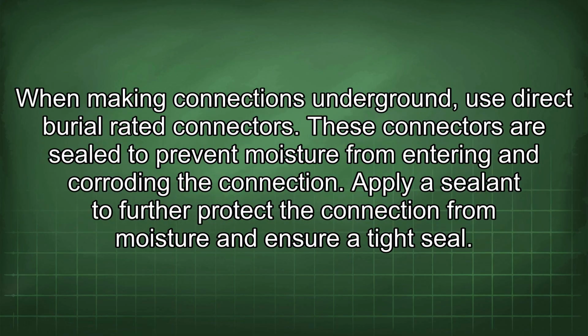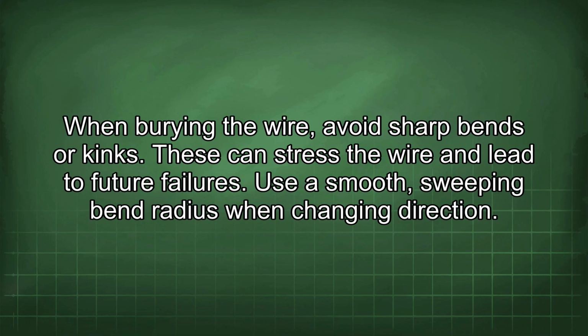When making connections underground, use direct burial rated connectors. These connectors are sealed to prevent moisture from entering and corroding the connection. Apply a sealant to further protect the connection from moisture and ensure a tight seal. When burying the wire, avoid sharp bends or kinks. These can stress the wire and lead to future failures. Use a smooth sweeping bend radius when changing direction.